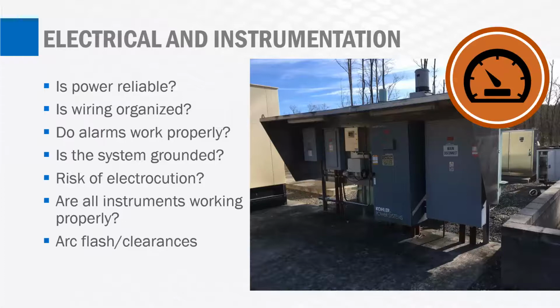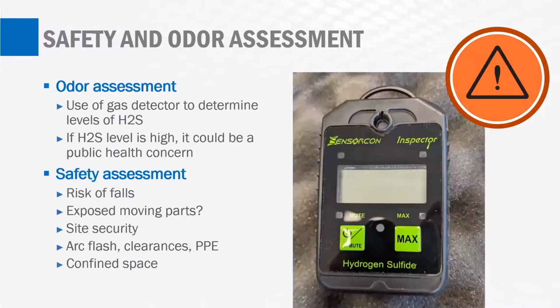Instrumentation. It's important to look at the instrumentation. In a lot of these pump stations, there are floats that are used. Sometimes those floats can get gunked up with grease and so forth. And it's really important to make sure that those floats are working properly. With grease especially, that can pose some big problems with your instrumentation. Arc flash. Is arc flash considered? So these are different things that can be looked at with your electrical and instrumentation systems.